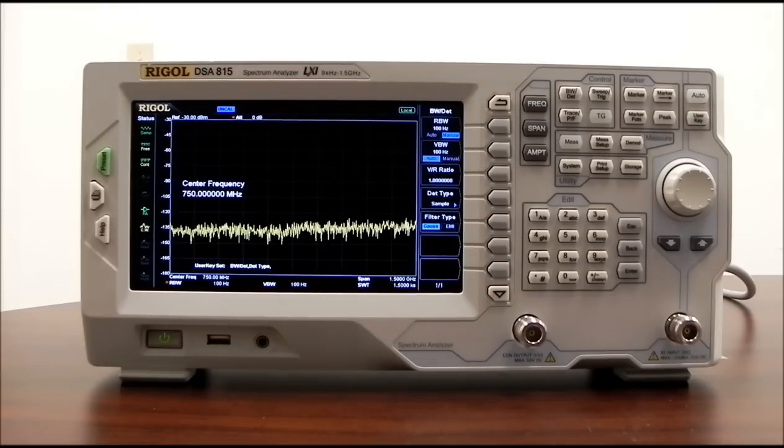And then VSWR, an available RF coupler and bridge. That's going to be DSA800-VSWR. And that's going to be a convenient way of showing the VSWR measurement for an antenna on the front panel or the display. Also available in the software area is an EMI toolkit that features an EMI filter, quasi-peak detector, and it also gives you some FCC resolution bandwidth values for qualification of FCC testing. Again, a very good tool for pre-compliance testing. We'll have some follow-on app notes in that area as well.